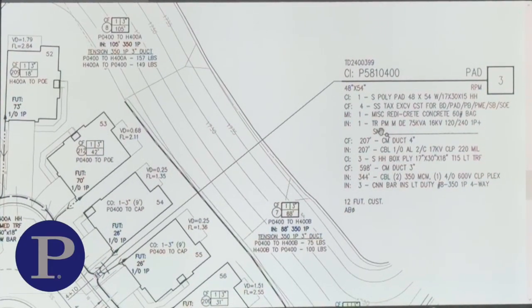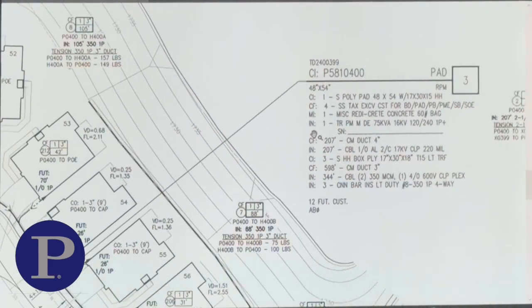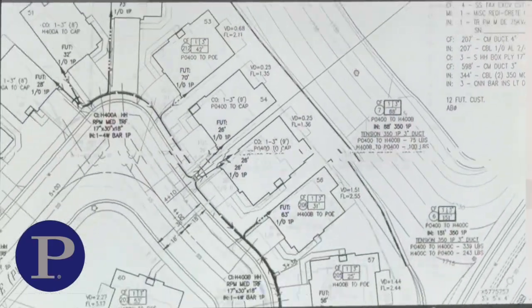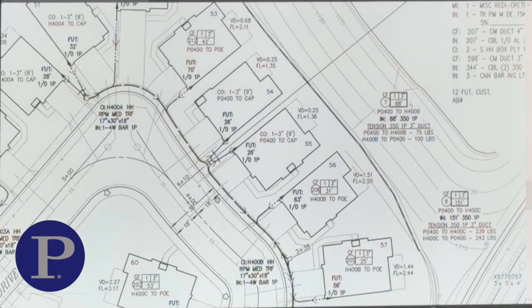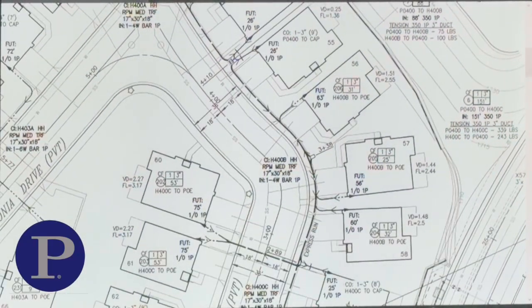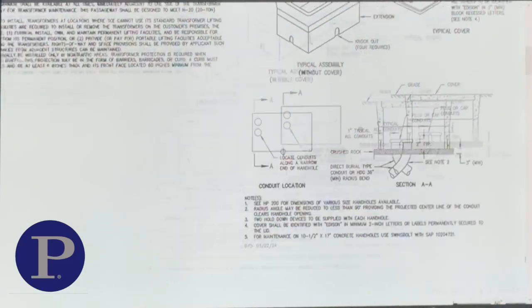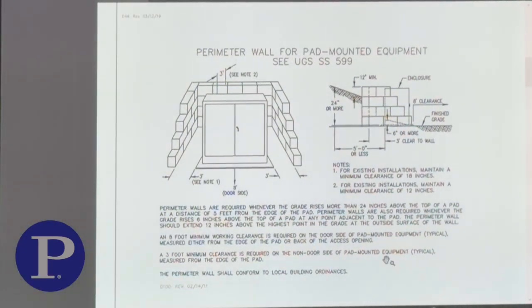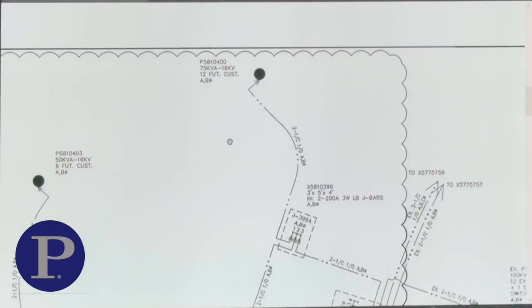If you look at this, this will also show us under the pad description, the transformer is going to be a dead end. That's what that DE stands for, dead end transformer, which means that's going to be the end of the line for this, which we know when we look at the single line, that is correct, because the single line shows us pad 400 as a dead end transformer, doesn't go anywhere from there.